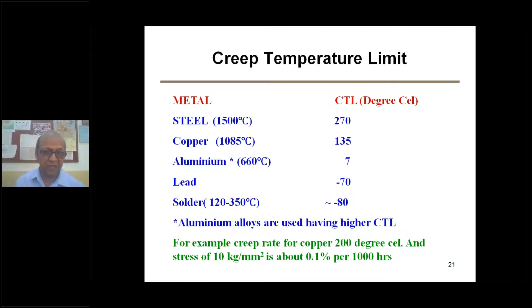Now look at this. Why did house wiring change from aluminum to copper? Have you analyzed why we have done it? Earlier, we were having only aluminum wiring. Where was the problem? Problem was only at the termination and joints, nowhere else. Because contact resistance increases at the termination or at the joint. When contact resistance increases at the termination or the joint, then there is a local temperature rise, which may cause short circuit, may cause heating. You have seen the example of many plugs burning whenever we are putting in a heater or geyser or something else, and it is because of aluminum. Why? It is because of the creep behavior, nothing else.